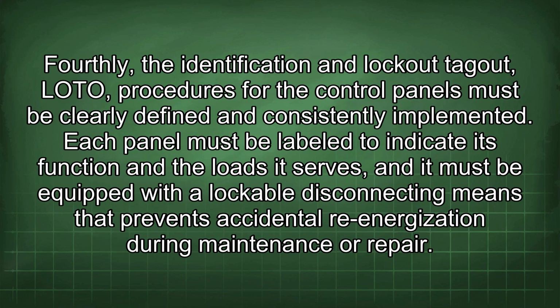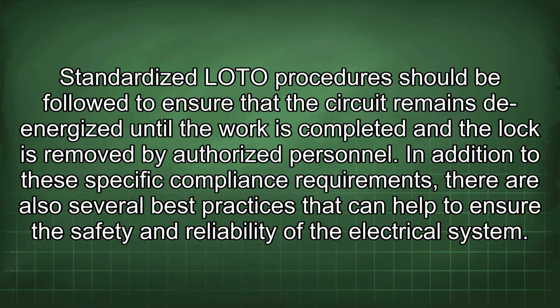Fourthly, the identification and lockout-tagout (LOTO) procedures for the control panels must be clearly defined and consistently implemented. Each panel must be labeled to indicate its function and the loads it serves, and it must be equipped with a lockable disconnecting means that prevents accidental re-energization during maintenance or repair. Standardized LOTO procedures should be followed to ensure that the circuit remains de-energized until the work is completed and the lock is removed by authorized personnel.